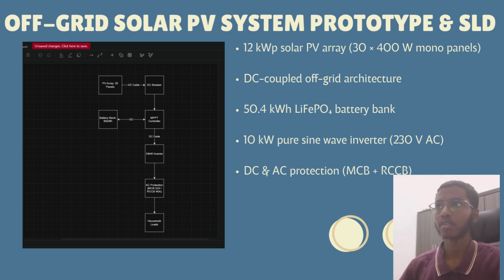Now I'm going to talk about the off-grid solar PV system prototype and single line diagram. This slide shows the system prototype and single line diagram of the off-grid solar PV system. Solar panels generate DC power, which is regulated by MPPT charge controllers and stored in a 50.4 kilowatt hour LiFePO4 battery bank. The inverter converts DC to 230 volt AC power for household use. Safety is ensured through DC circuit breakers, a 32 ampere MCB and a 40 ampere RCCB, providing reliable and safe standalone operation.